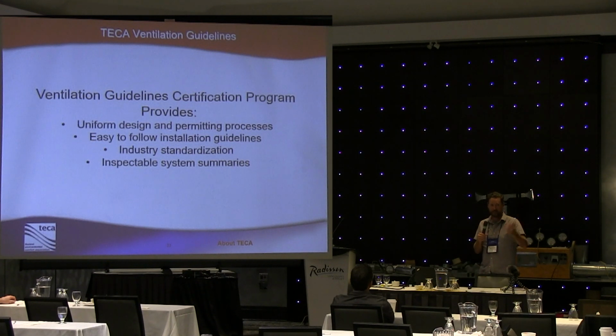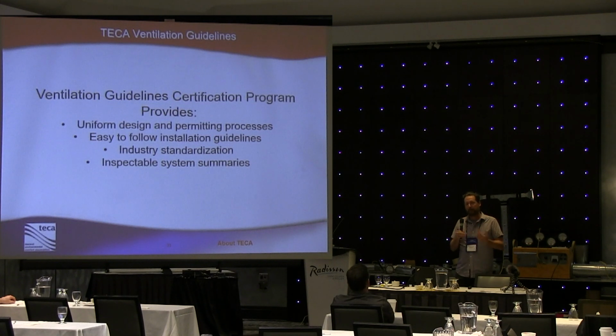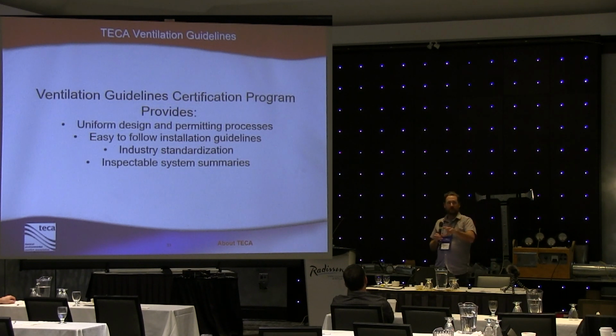You know, especially when you get into some of these cold climate areas, right? You get up into the Okanagan and that, you may need multiple kilowatts of electric heat. It might not even be available to you. You may only have a 100 amp service, and you might need 60 amps of it dedicated for a makeup air heater. So there's a lot of pitfalls to the ventilation system if it's not designed and then adhered to through the construction process.